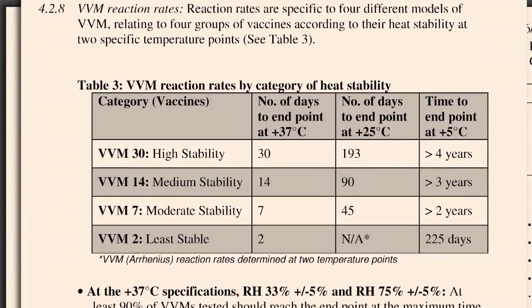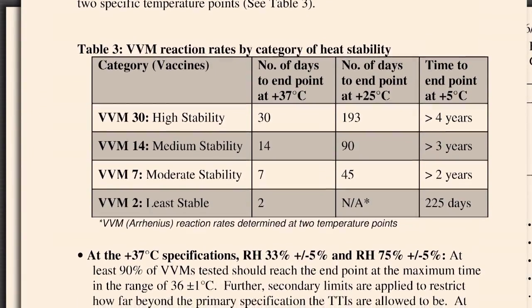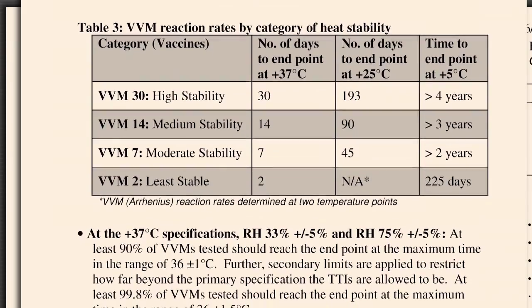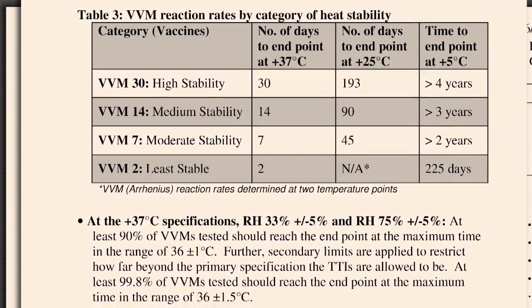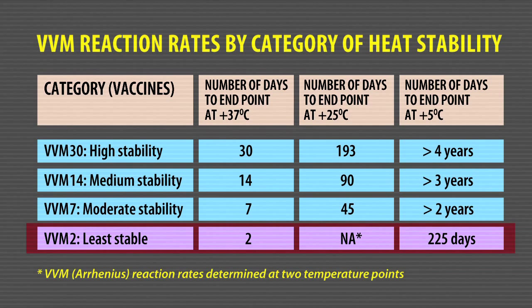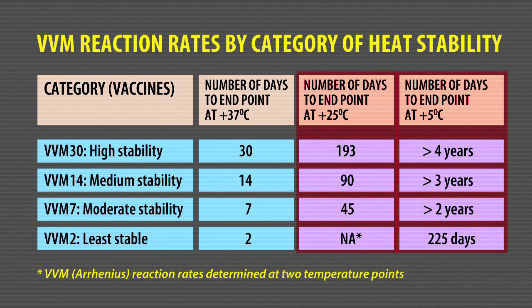This table here summarises different levels of stability characteristics of vaccines and types of VVMs that are assigned to them. VVM2 for the least heat stable vaccine reaches its end point in two days at 37 degrees. VVM7 reaches its end point in seven days at 37 degrees. And VVM14 in 14 days at 37. VVM30 for the most heat stable vaccines in 30 days at 37 degrees. On this same table, you can also see the various end points when the vaccine is exposed to 25 degrees as well as 5 degrees.